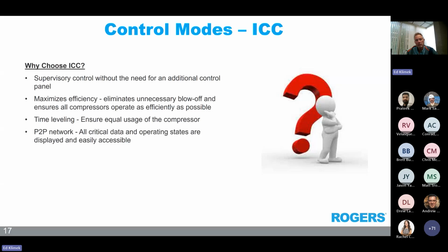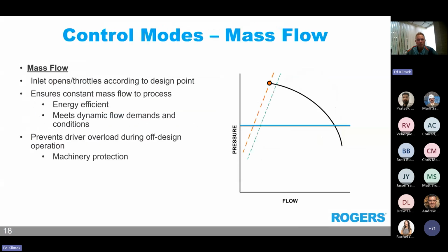Another common control mode is mass flow. So mass flow controls and measures the mass flow at the discharge line to the plant system by adjusting the inlet valve. It maintains the user's targeted mass flow, ensures compressor operation efficiency, and avoidance of surge. So I'll animate this a little bit here.